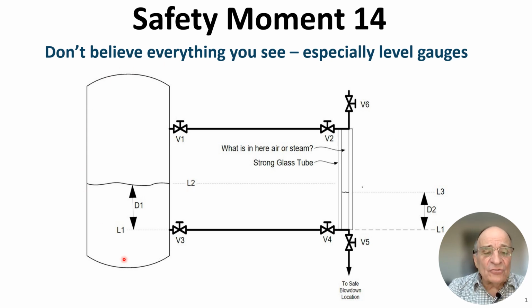Now, most times it won't matter too much, because if you're off by a half inch or so on a 12-inch gauge, it's not really all that important if you're trying to keep 6 inches, whether you have 5½ inches or 6½ inches. But it is a phenomenon that you need to be aware of. Also, let's say this was a water level gauge. What about the debris and corrosion that ends up in this tube? Are the valves open? Was this serviced and the valves opened? You want to make sure that these valves are open as well and not plugged. You have blow-offs that allow you to check that, but it is important that these gauges work properly.